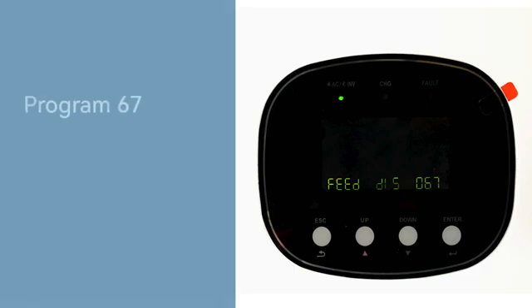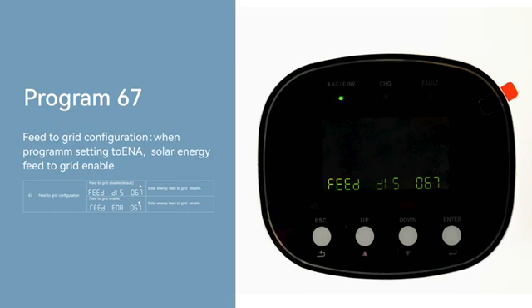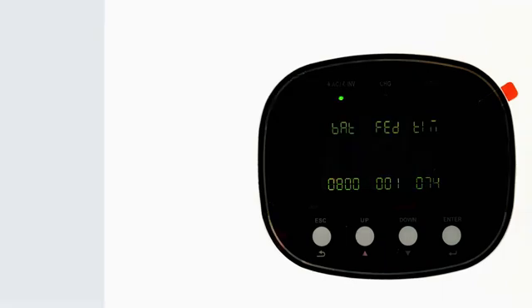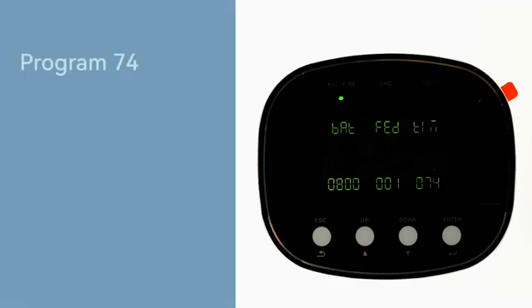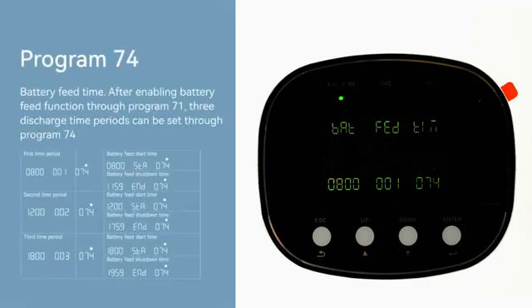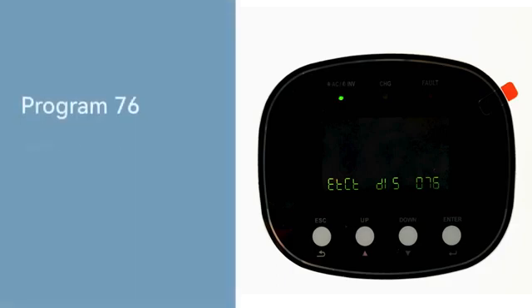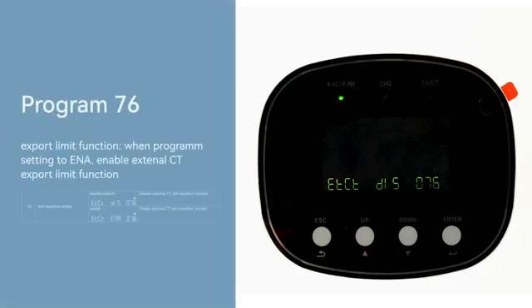Program 67 Feed-to-Grid Configuration: When set to ENA, solar energy feed-to-grid is enabled. Program 74 Battery Feed Time: After enabling battery feed function through Program 71, three discharge time periods can be set. Program 76 Export Limit Function: When set to ENA, external CT export limit function is enabled.